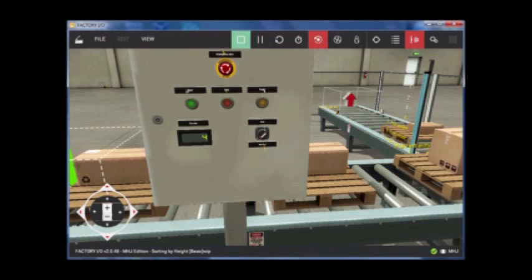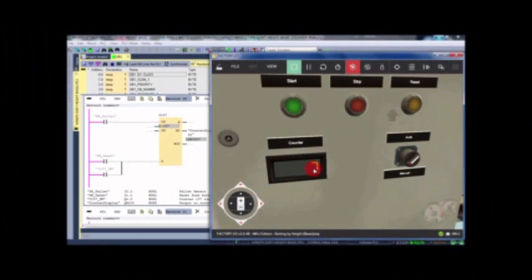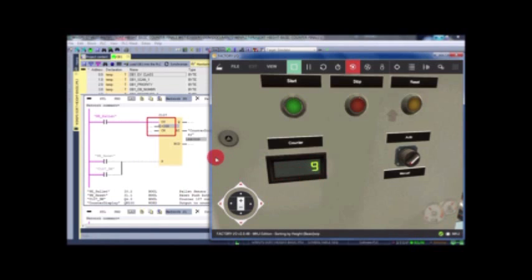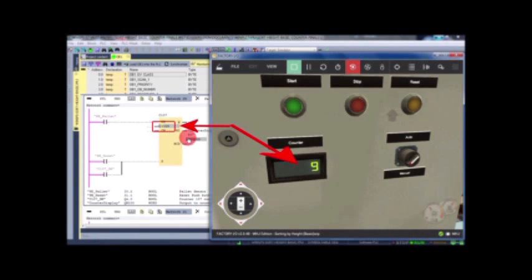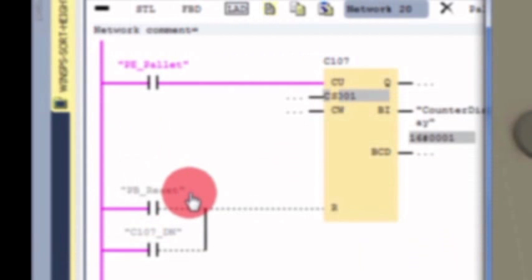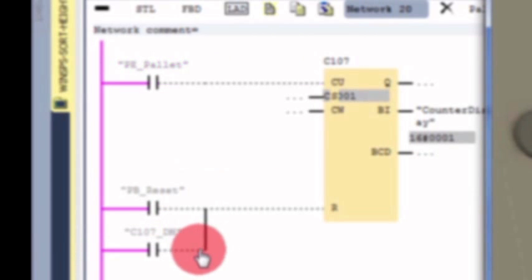Let's pull back the curtain and see what controls this counter display. In the Siemens simulation software we have a counter function. You can see the current value of counter 107 matches the displayed count via the binary integer output from the Siemens PLC counter. Counter number 107 is programmed to reset if the operator's reset push button is pressed or the internal counter done bit becomes true.